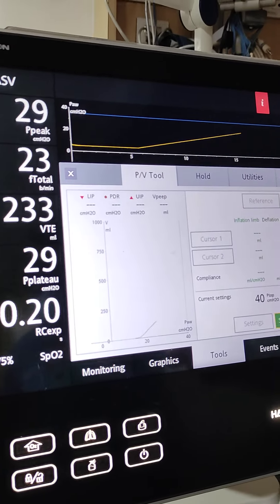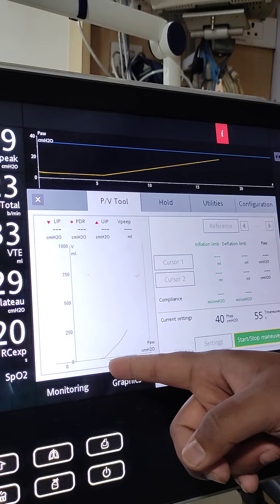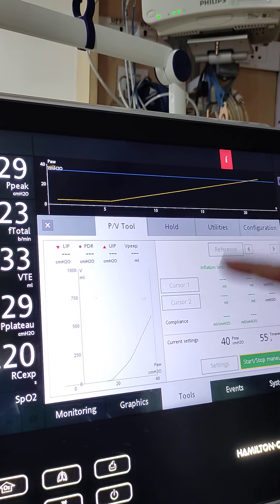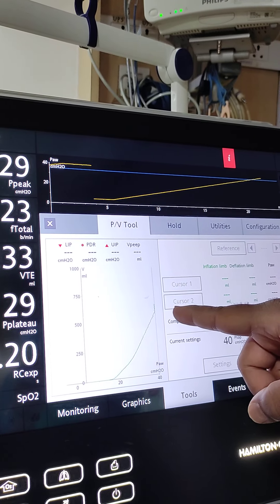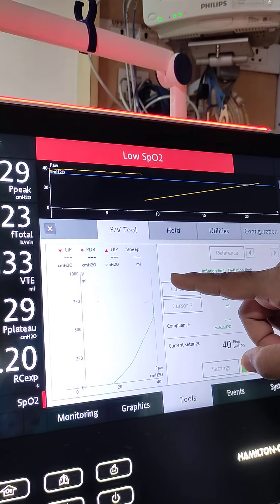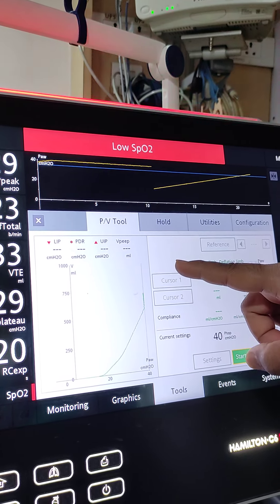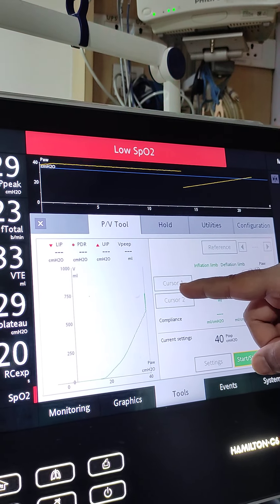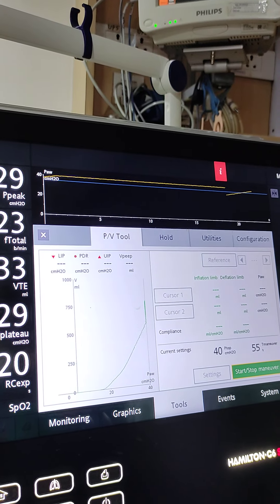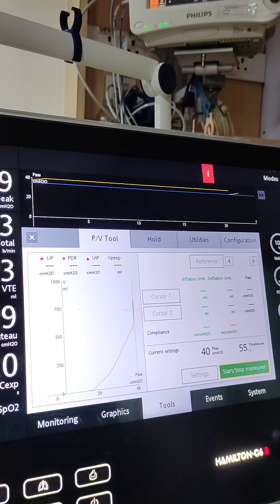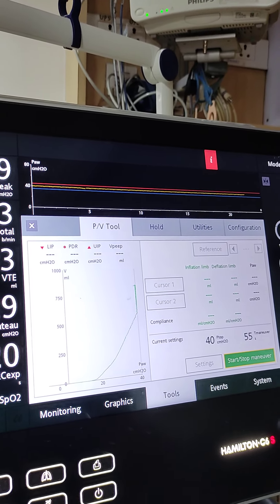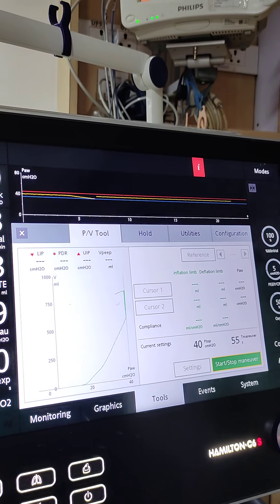Now it started — see, it started the recruitment maneuver. It started at 5, now it has gone up — it is going up to 40. You have to look at the saturation now. It has paused — that is 25 seconds. This is the volume that I am gaining when I am recruiting. In 5 minutes time the saturation should go up.